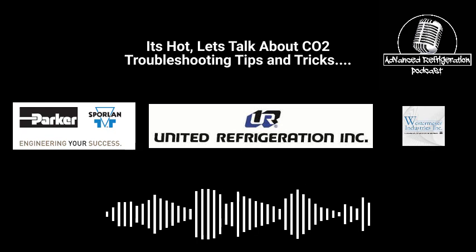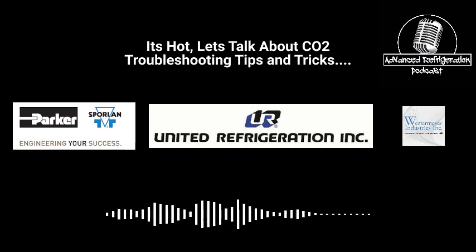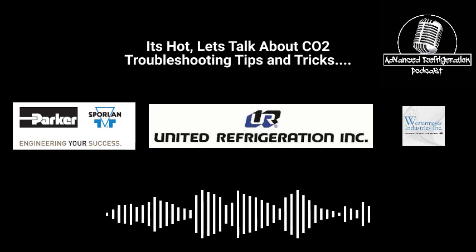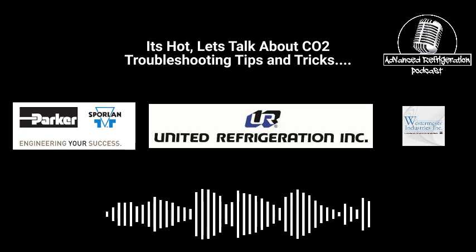These racks were failing. So what Kysor does is they don't even have an optical eye, at least on the newer racks. They're just cycling on time, which is genius. Just keep it rolling. They're getting all that oil out of there. No, that's good. The only thing is you'd have to make sure you had it in there where something shuts it down, right? Well, they do. They have it in there. So if the medium temp compressors aren't running, or if there's a high pressure condition in the receiver, it shuts it down.